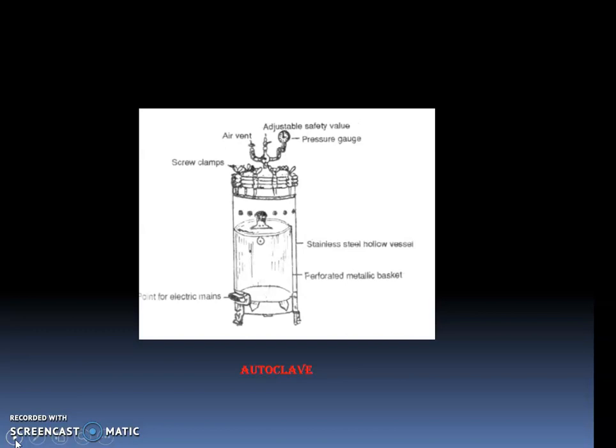So we'll start with the first equipment. The first equipment is the autoclave. Autoclaving is nothing but a process of heat in which saturated steam under pressure is allowed to penetrate through the material at a temperature of 121 degrees Celsius for 15 to 20 minutes, and the pressure is 15 lbs per square inch. The measurement of time begins when the temperature of the material being sterilized reaches 121 degrees Celsius.